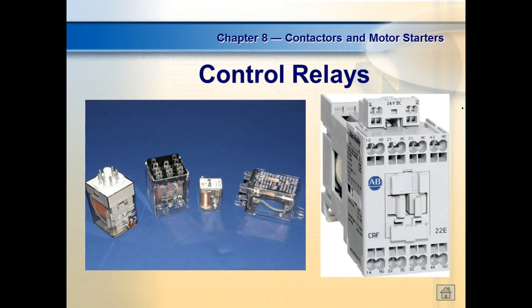So we have a bunch of standard sockets out there. There's little knobs on these too, so they're keyed. You just can't cram them in there any way you want to. Normally, if you looked at this thing, it would be round, and then it'd have a notch sticking out the side, and your socket would have that same notch. Some of y'all found the socket for our off-delay relay, and it was just empty. You could see the notch inside the socket.